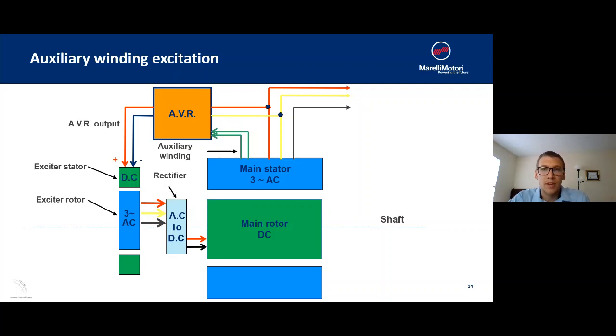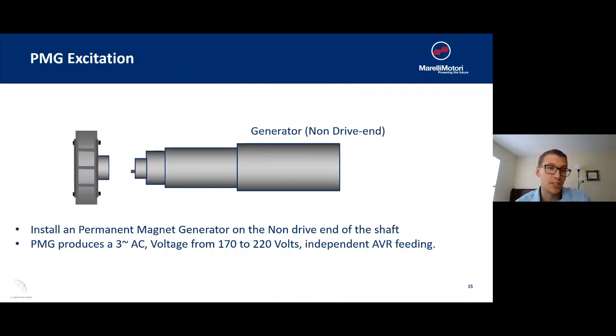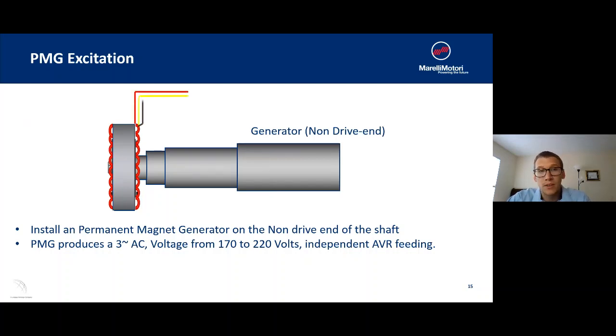Another type of excitation we're going to be looking at is PMG excitation systems. A PMG excitation system is when you install a small permanent magnet generator onto the non-drive end of the shaft. This PMG produces a three-phase AC voltage anywhere between 170-220 volts depending on which one you get. And it's going to feed the AVR independent of the rest of the system.